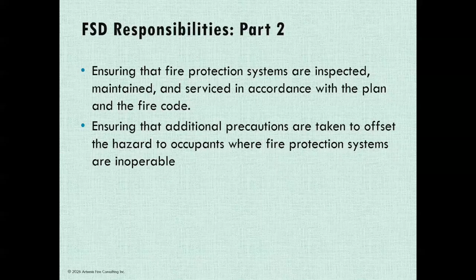They are also responsible for additional precautions being taken to offset hazards to occupants where fire protection equipment is inoperable. This could include checking the fire safety plan and the fire code when systems need repair, advising the fire department of the system's status, and if needed, instituting a fire watch, meaning a 24-hour patrol of the building to notify residents in the event of an emergency, as long as the system is inoperable.